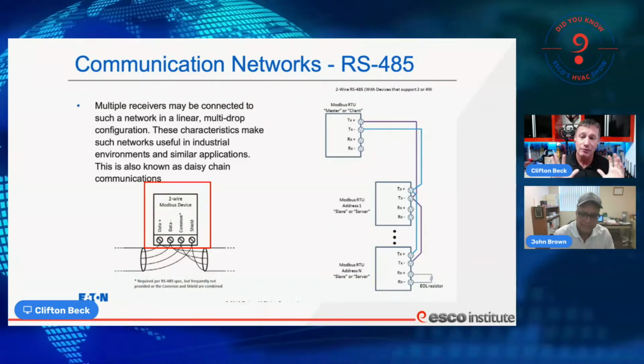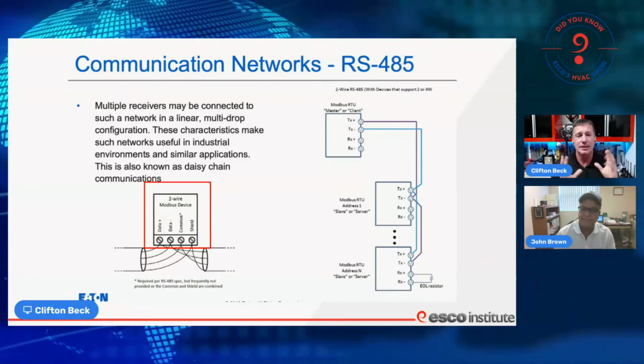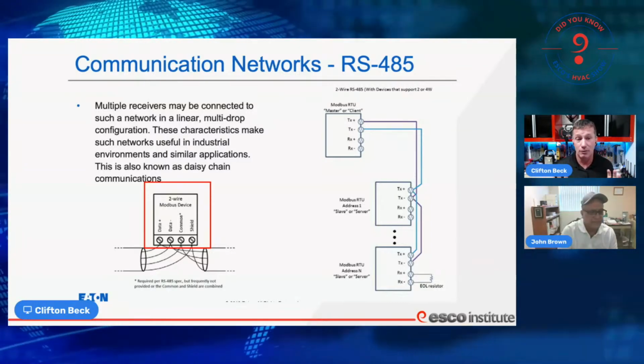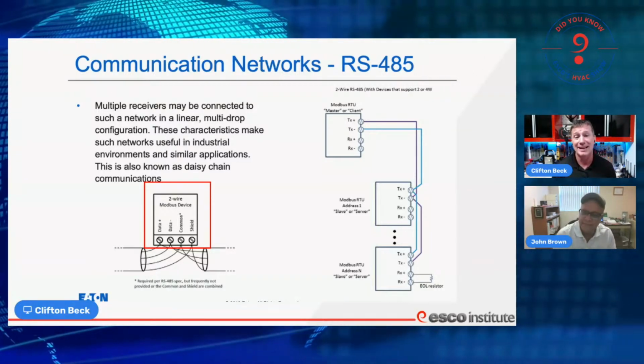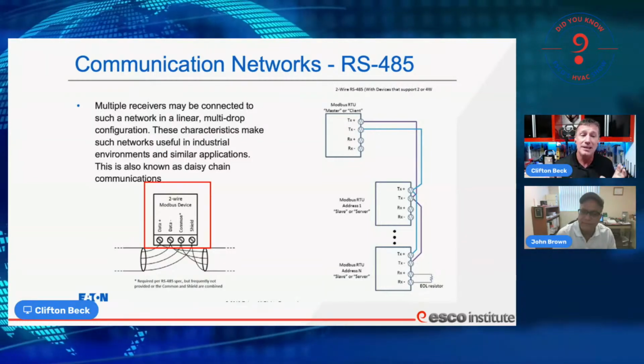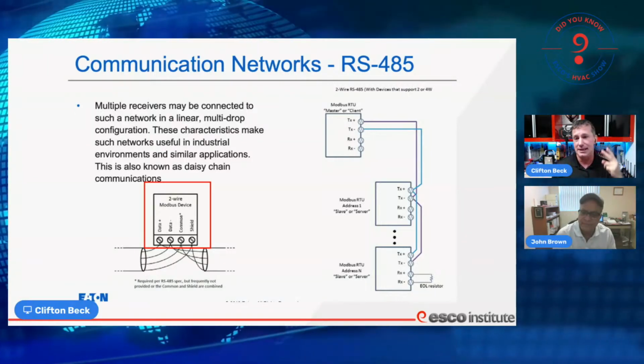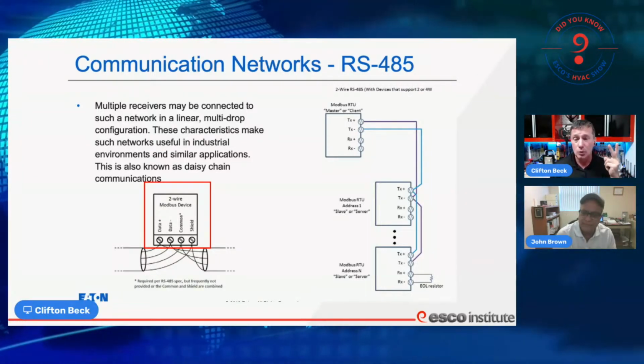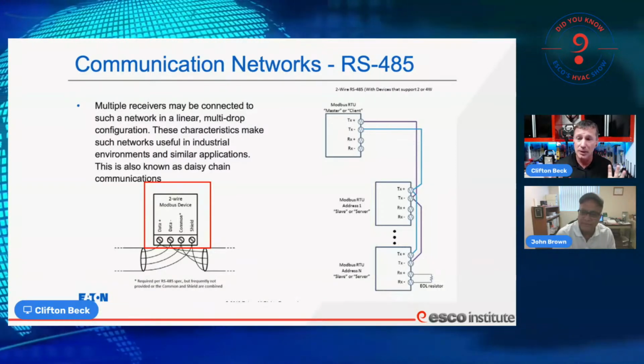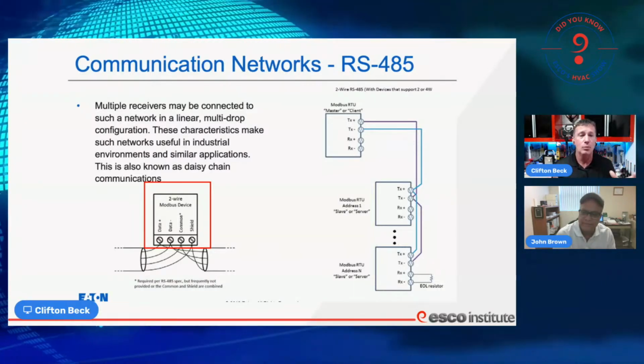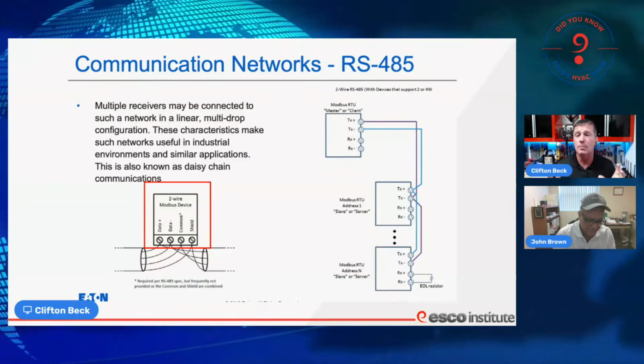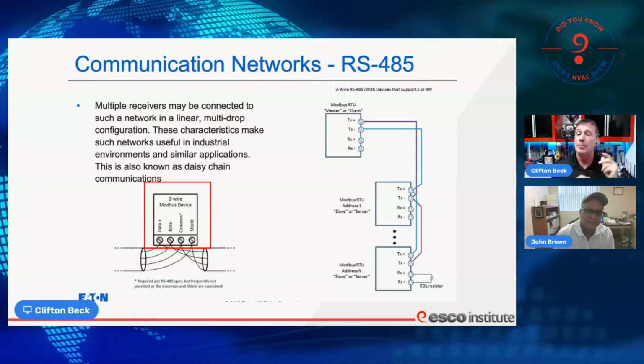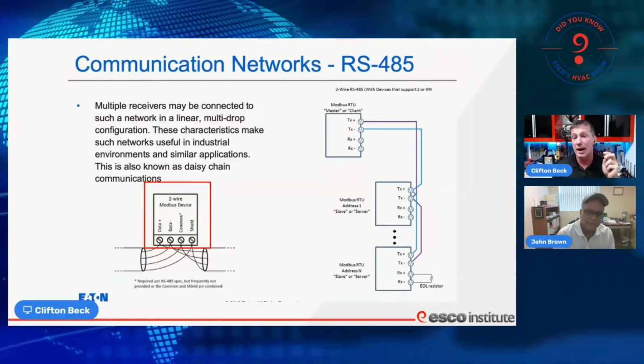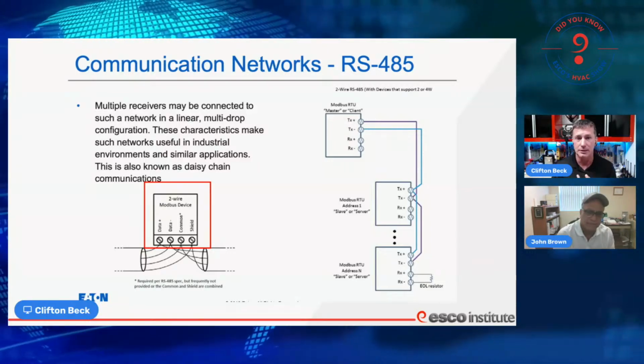If we look at this reference from Eaton, it will tell us that the RS-485 system has been around for a very long time, really developed back in the 1980s, and it's based on a 5-volt DC two-wire principle — two-wire communicating system. It could be up to 4, but most of the time we're using 2 wires to develop that 5-volt DC signal, in reference to a ground or a common landed ground.